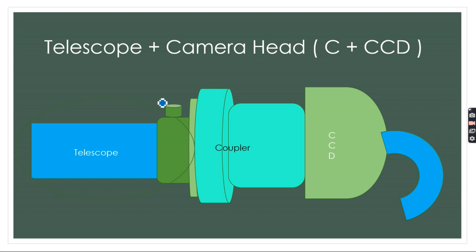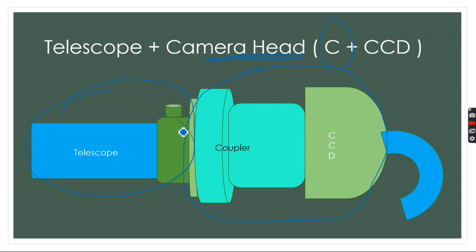To clarify: the telescope alone refers to just this part. If we attach something to the proximal part of the telescope, that portion is known as the camera head. The camera head contains two things: the coupler — which is the attachment between the telescope and the CCD — and inside the camera head, proximal to the coupler, is the CCD or charge-coupled device. It captures and analyzes the image and sends it to the monitor for display.